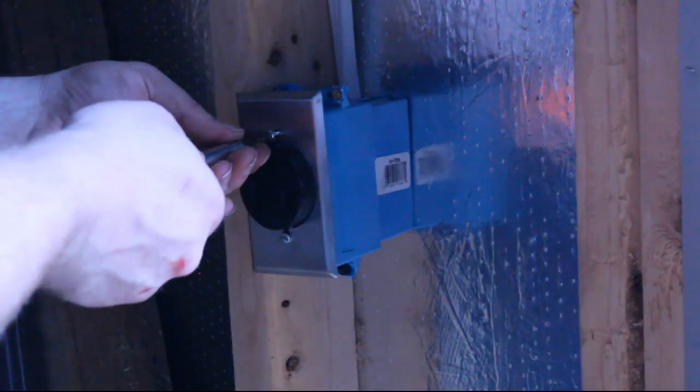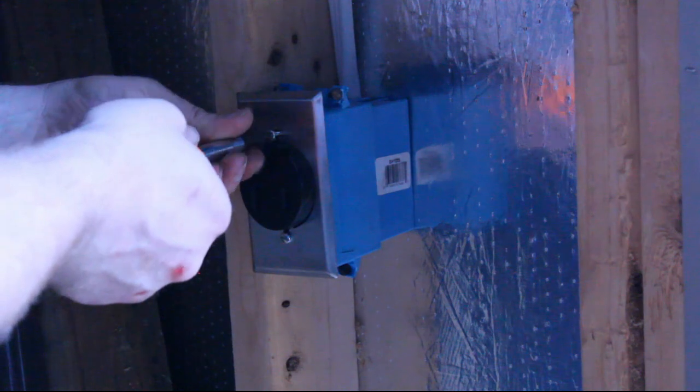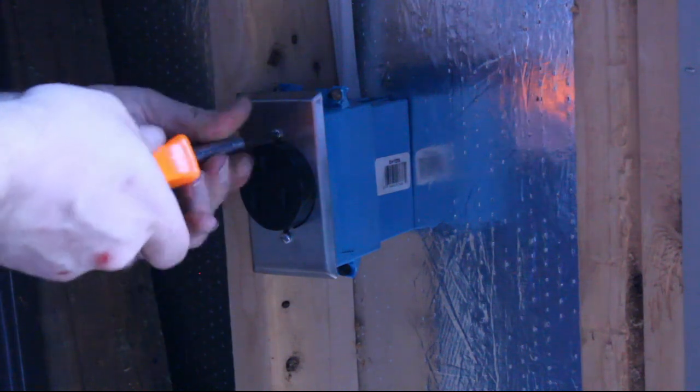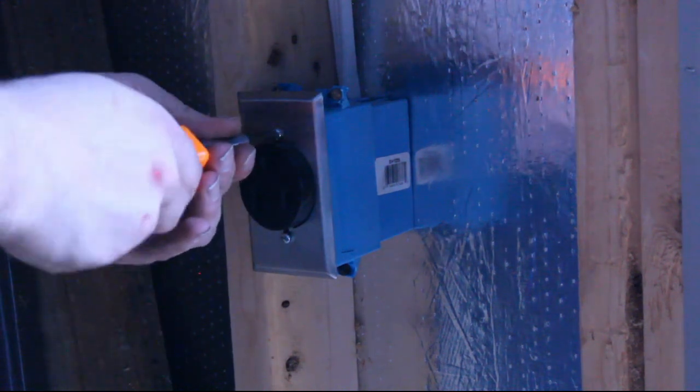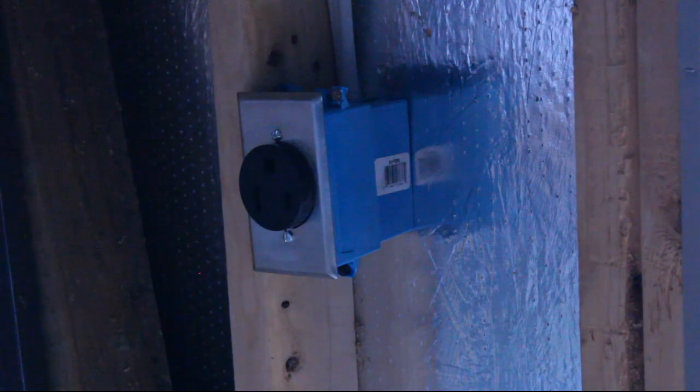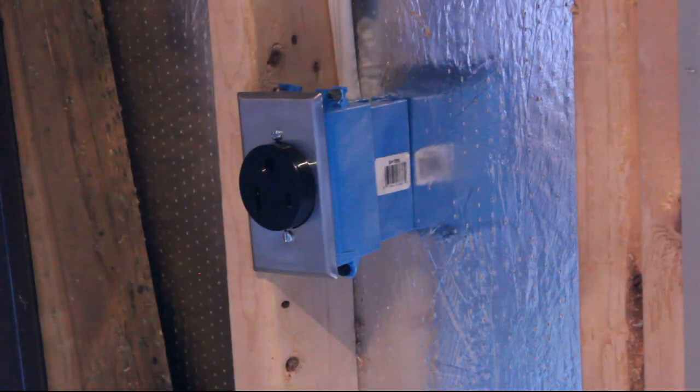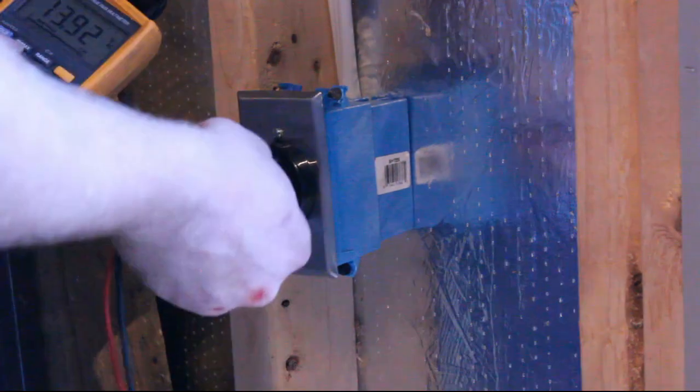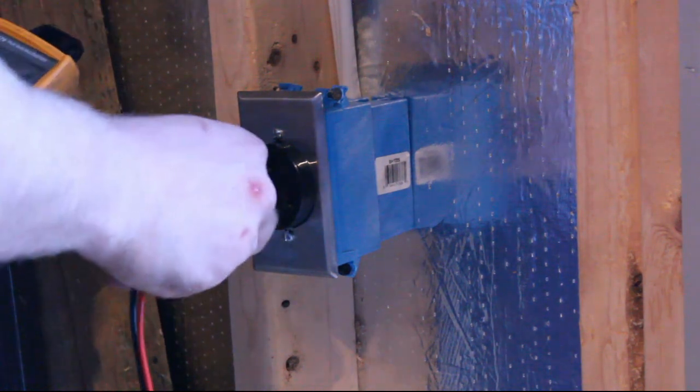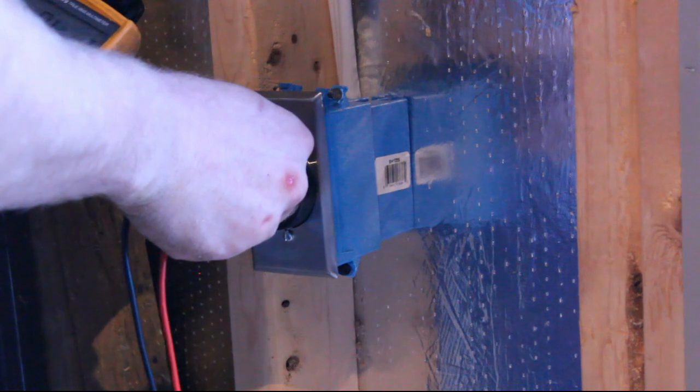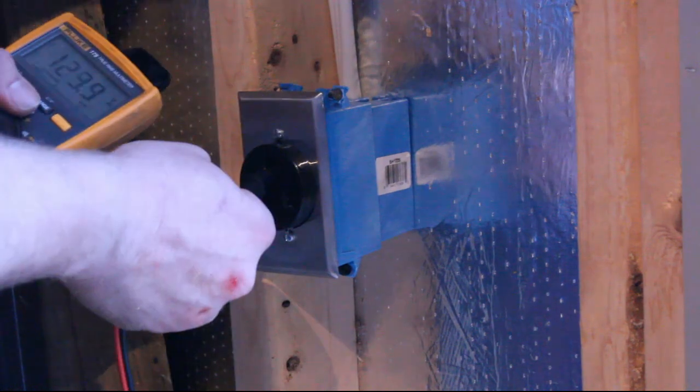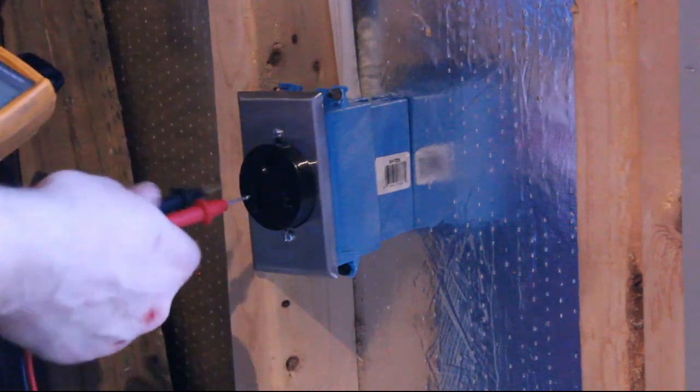All that's left to do is put the wall plate on and flip the breakers. Now I just need to make sure that I'm getting the right voltages. Phase to phase, I should be getting between 220 and 240 volts AC, and from each phase to ground, I should be getting 110 to 120. That's what I'm seeing here, so I know my wiring is good.